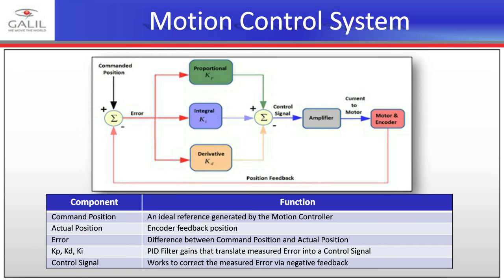A quick overview of a motion control system: you have a motor to be controlled in an application, encoder feedback which is fed into a PID loop, and that loop outputs a control signal to an amplifier that provides a corrective action to minimize error between the motion profile and the encoder-measured position. Standard or current technology uses an analog signal — the control signal and feedback are primarily what we'll be speaking about today. Standard control uses either encoder feedback or analog feedback for position information, and then an analog control signal to the amplifier, typically plus or minus 10 volts, which is translated into a current or torque in the motor.